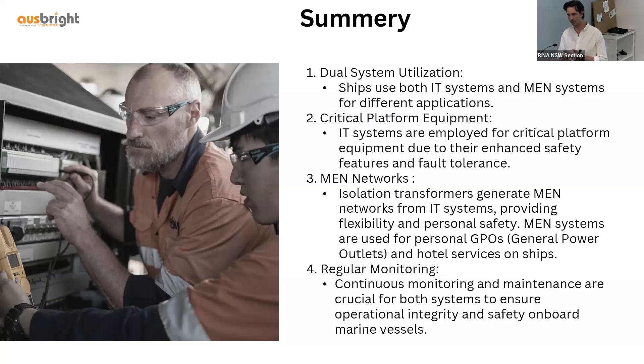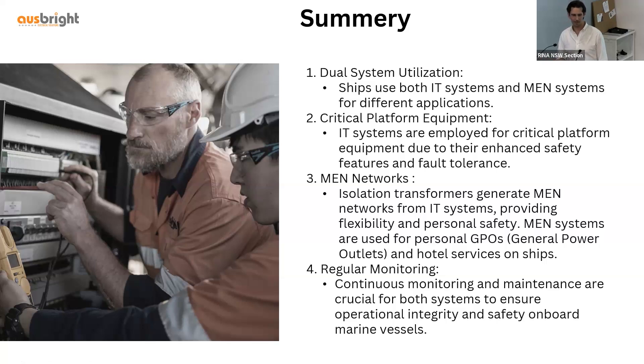Critical platform equipment is always going to be on an IT Earth system for the protection it provides. Regardless of either system, electrical systems degrade — especially on ships due to heat, seawater, and harsh conditions. Insulation will break down; nothing lasts forever. Regular maintenance, monitoring, and testing of earthing systems are all crucial to the integrity of the system. If you just set and forget, the system is not going to save you completely — you always need a level of maintenance and continuous monitoring.